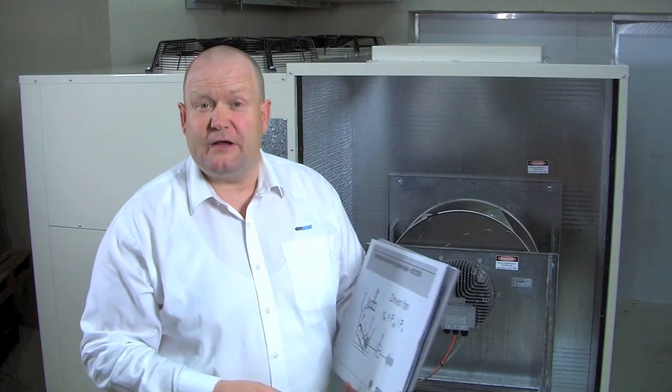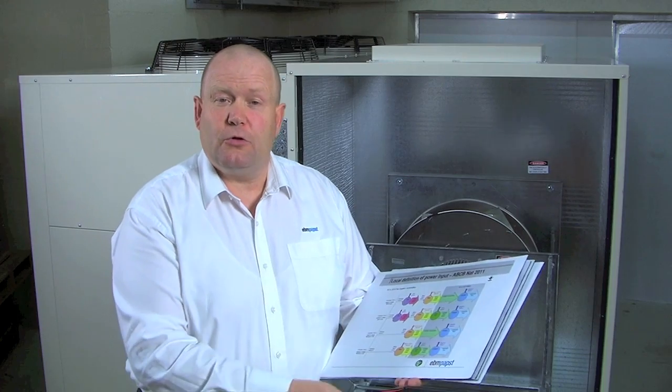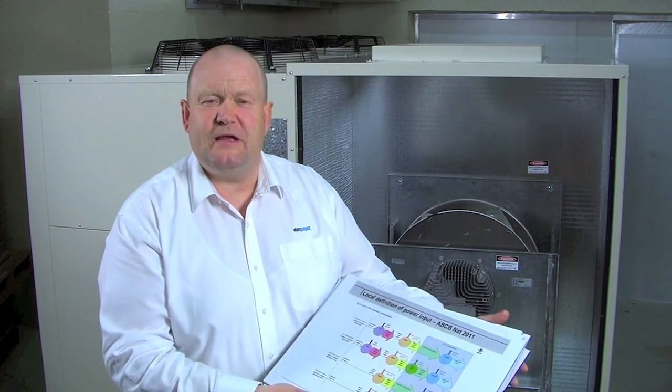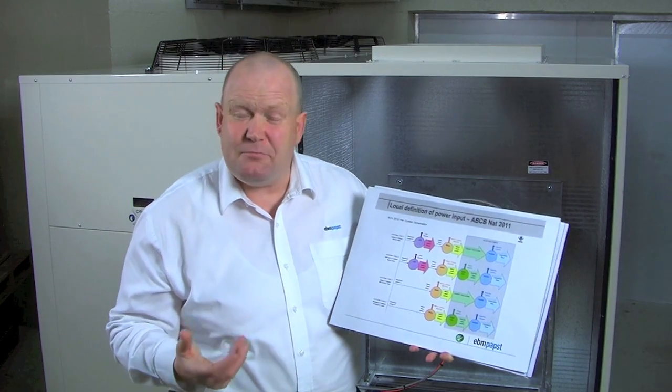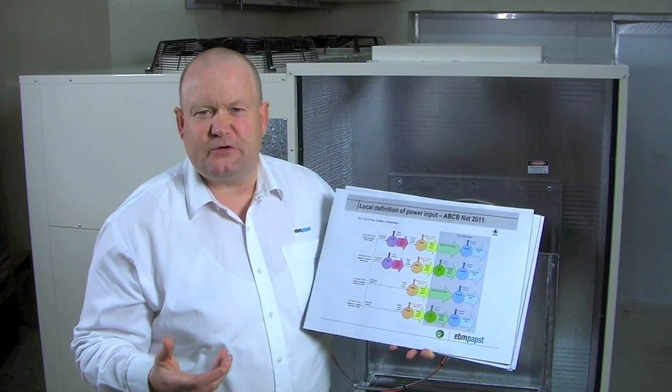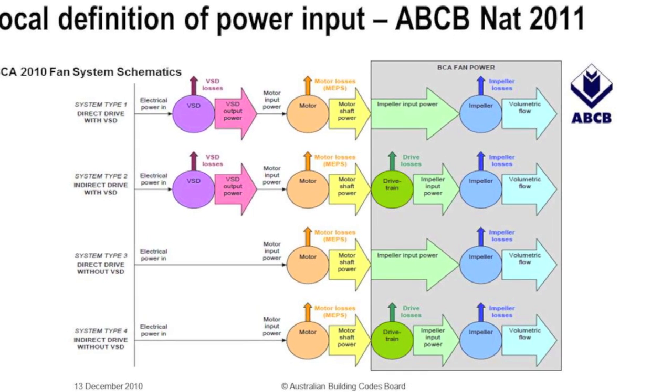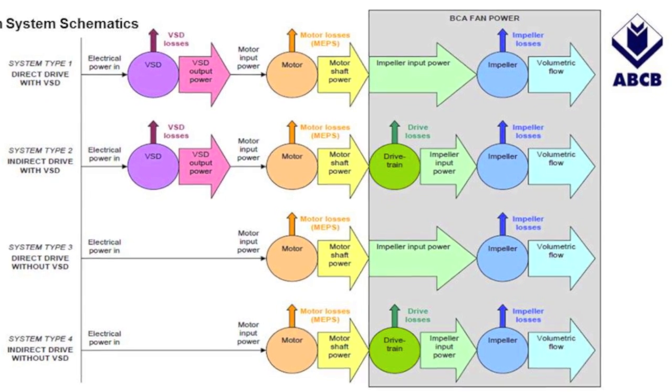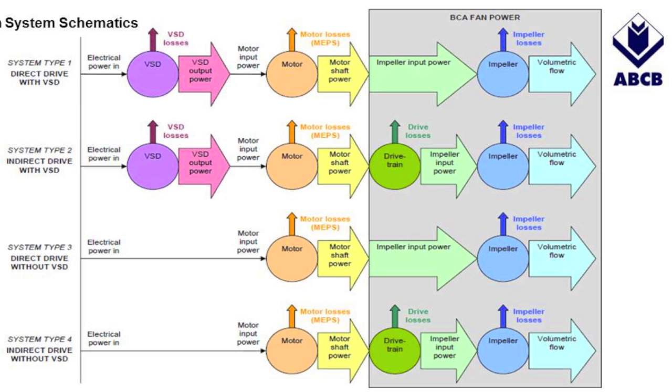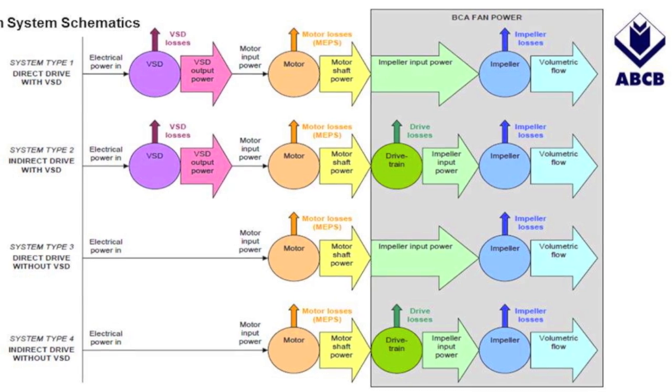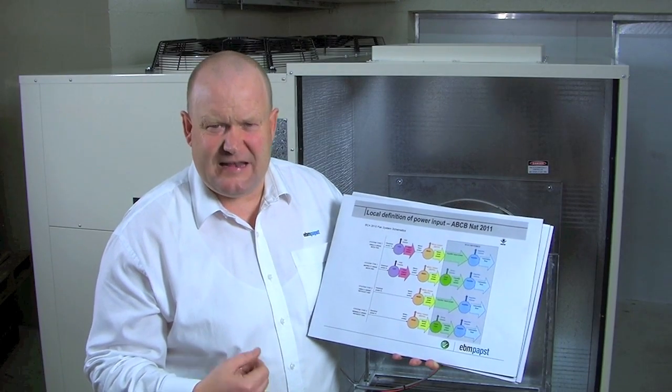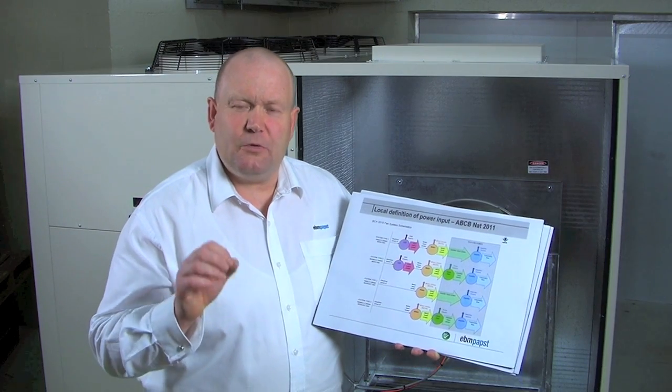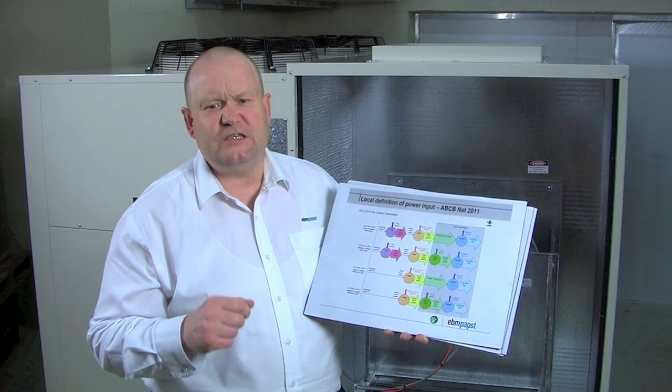Now, locally what's happening in Australia? In Australia, the local authority affecting fan minimum efficiency is the building codes of Australia, and here I have a graph which defines the fan input power inside the building codes of Australia. On the right hand side, the grey out area is the area which the building codes define as fan input power, and you can see that's the shaft power. You can see on the left hand side the consideration is taken towards the whole fan system, but only the right hand side, the fan input power at the shaft, is defined as fan input power. Now, this is in complete difference to the international standards and we need to be aware of that.